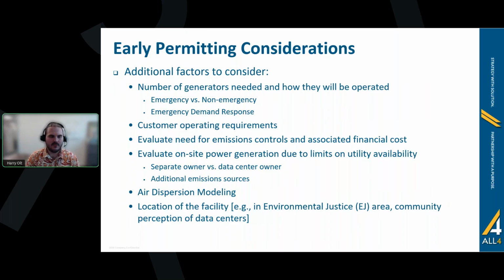Customer operating requirements, such as minimum number of hours of testing per year, will influence air permitting and should be considered, the same for emissions controls. Understanding whether they'll be required based on the state, the customer's preferences, and/or to help avoid major source thresholds impacts not only air permitting but also capital costs for the project.